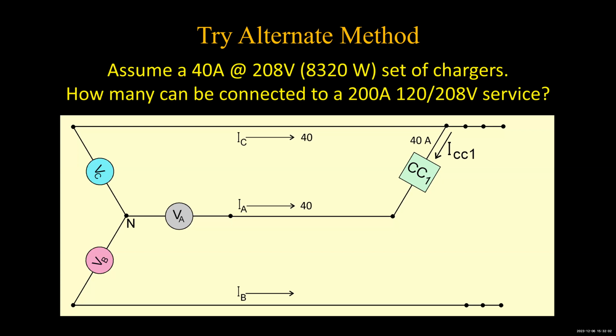And then we connect another one. And now we've got 40 amps coming out of A that feeds charge controller 1, and another 40 amps from A that feeds charge controller 2, and 40 plus 40. Wait a minute. 40 times 1.732, why not 40 plus 40? Why not 80? Anybody know the answer to that? Of course, the answer is that just as these drawings are 120 degrees out of phase, so are the currents. So in this case, 40 plus 40 equals 69.3.